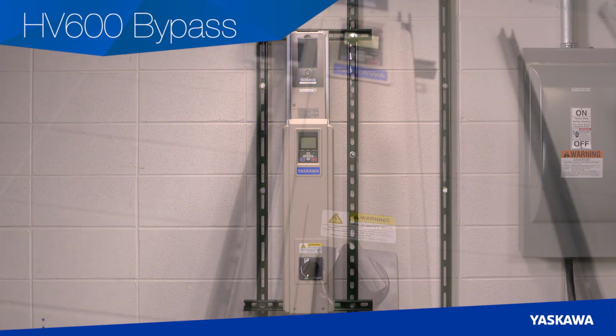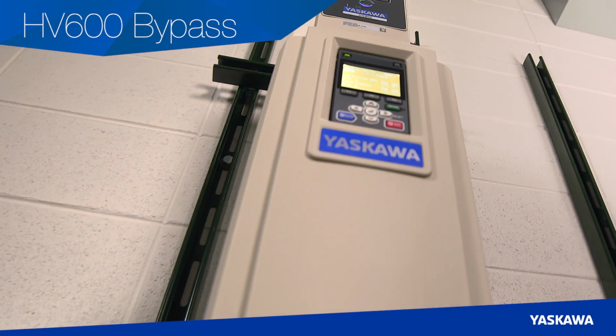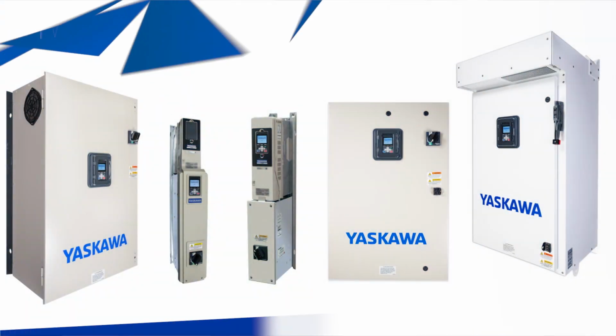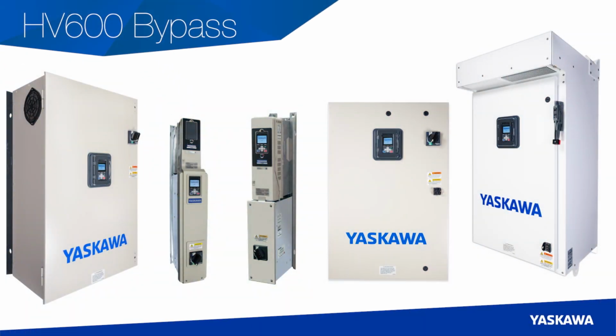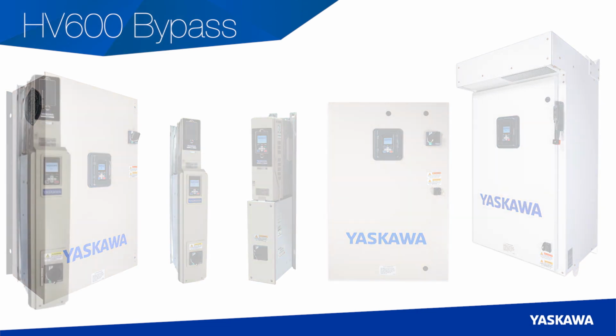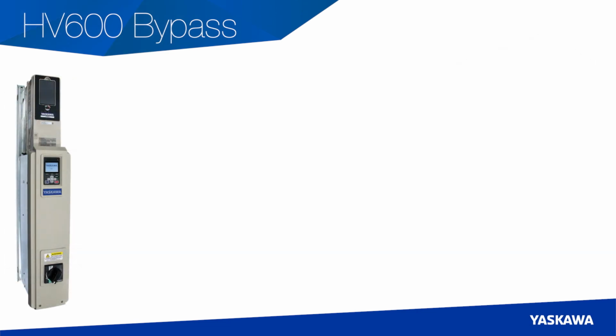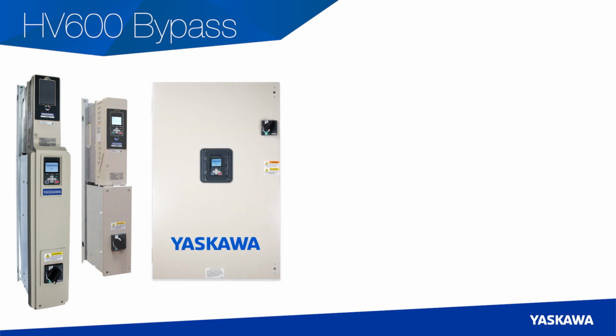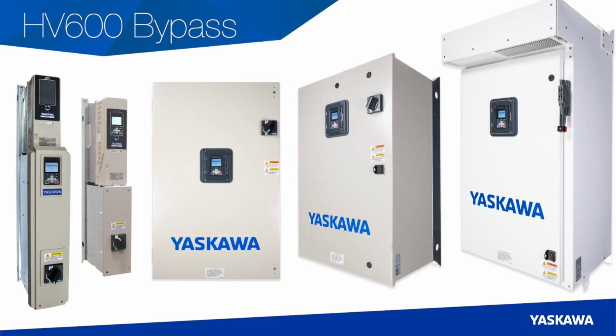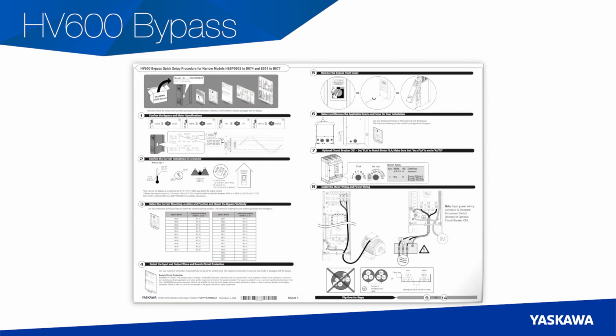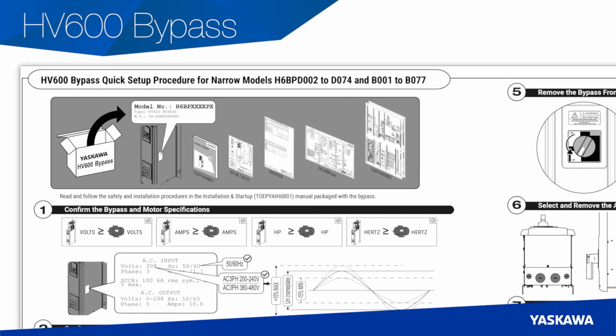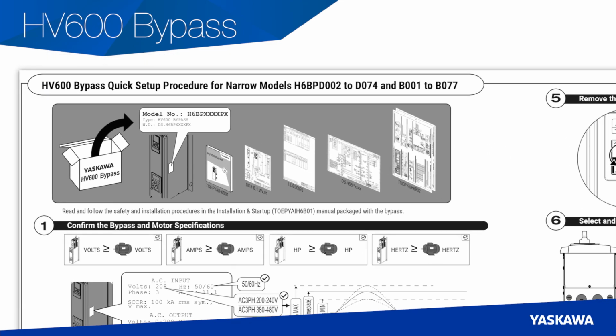In this startup, we'll be using the Yaskawa HV600 UL Type 1 narrow bypass. Yaskawa has many offerings when it comes to bypasses and configured units. These range from UL Type 1 narrow bypass and configured UL Type 1, 12, and 3R enclosed bypass and configured units to meet the needs of our customers. The quick setup procedures differ slightly between models and enclosure types. Always use the quick setup procedure that's packaged with the product. The overall installation process is very similar between models.